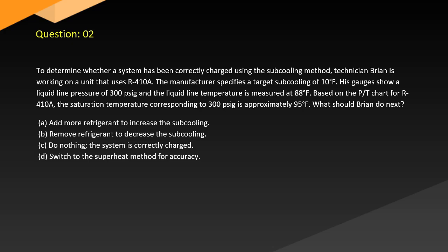Question 2. To determine whether a system has been correctly charged using the subcooling method, technician Brian is working on a unit that uses R-410A. The manufacturer specifies a target subcooling of 10 degrees. His gauges show liquid line pressure of 300 psig and the liquid line temperature is measured at 88 degrees. Based on the PT chart for R-410A, the saturation temperature corresponding to 300 is approximately 95 degrees. What should Brian do next?